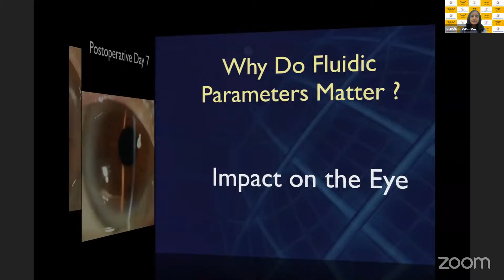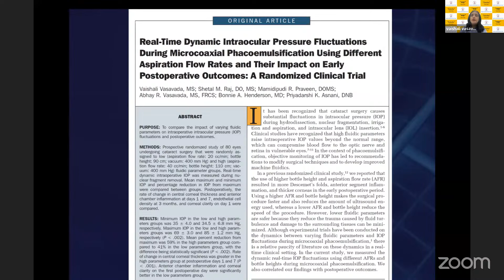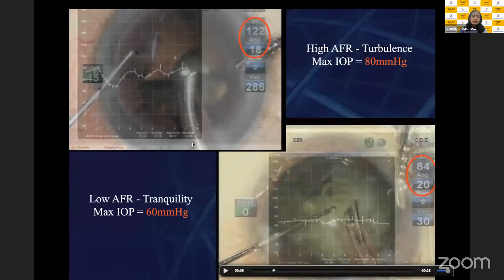So I think moving on, why do these fluidic parameters, so much I've been talking about flow rate and vacuum, why do they matter? Because we did a lot of studies and have published about 3 articles where if you have a high flow rate, that means 40 cc per minute, you automatically need high vacuum. And in which case you will see that there is a lot of fluctuation happening on this graph. So this white graph is the actual intraocular pressure within the eye. This is the sensor which was inserted and it is measuring the pressure. So when you have a high flow rate, obviously because the output is more, you need more input. So the pressure can go as high as 80 to 90 millimeters of mercury.